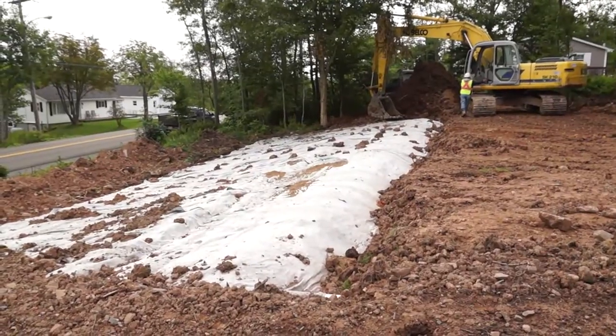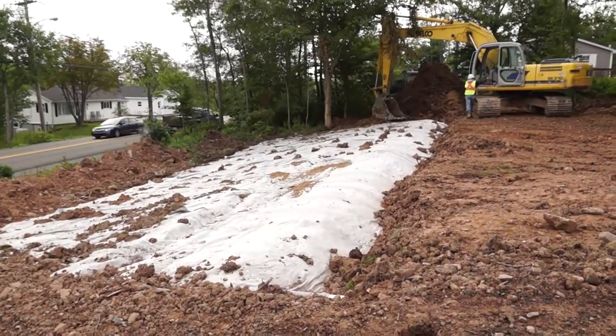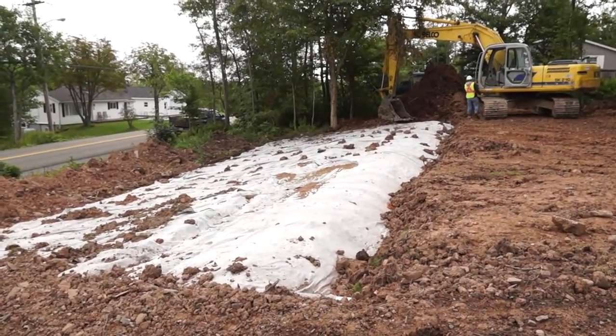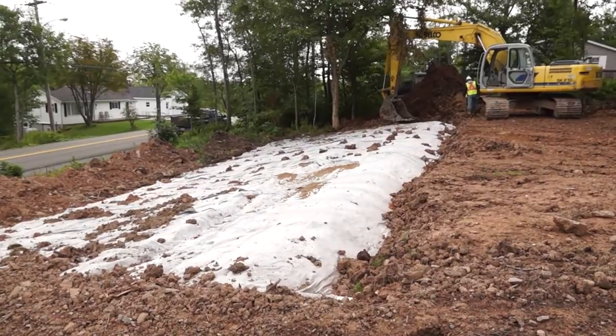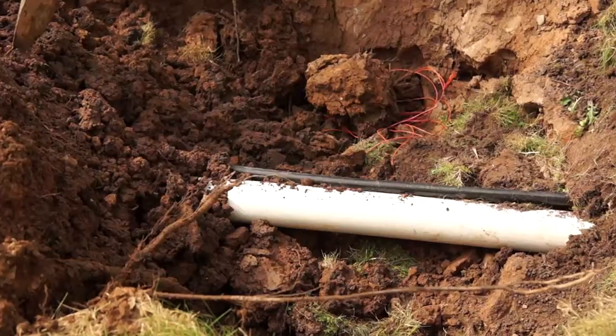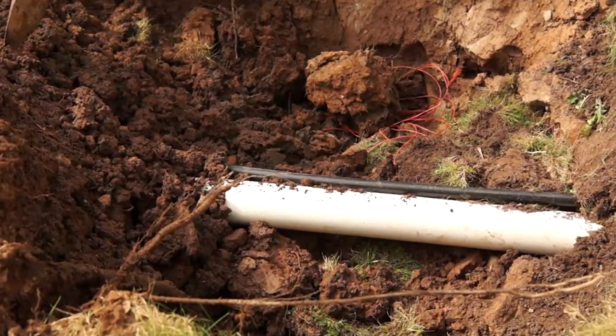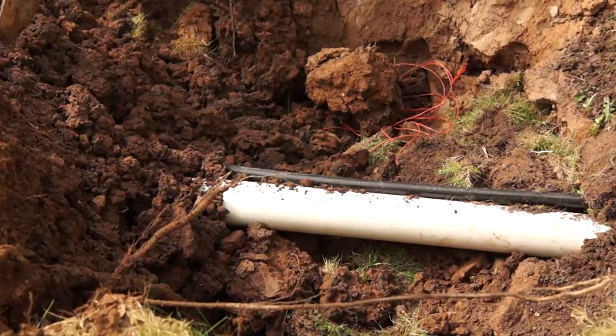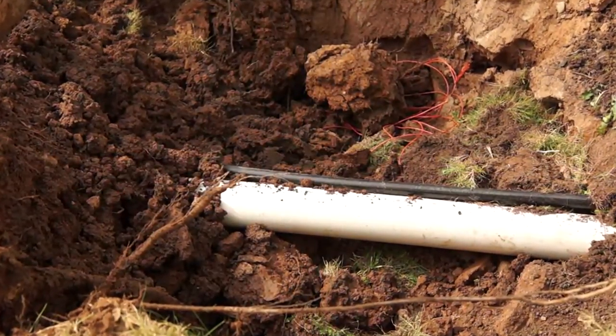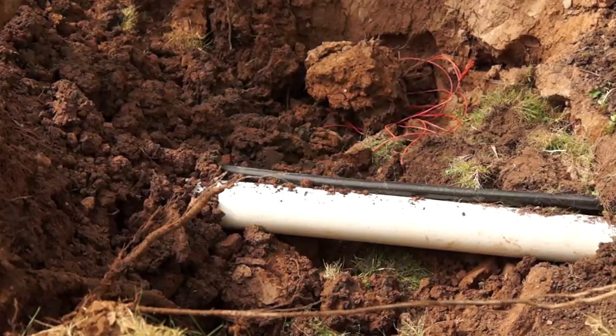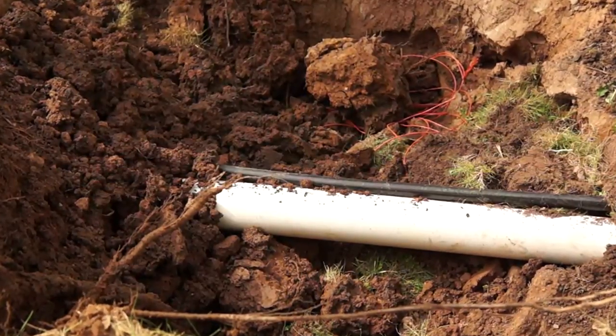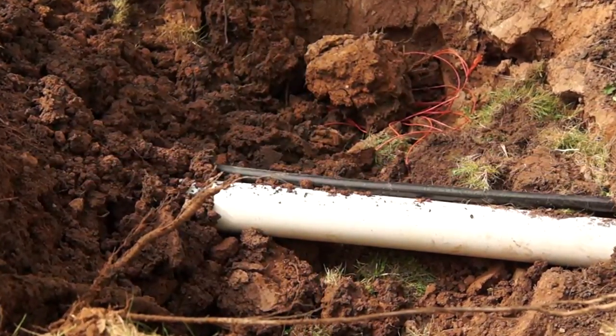The distribution trench and filter bed are covered with a geotextile material and left open. Water softener discharge may cause problems with the septic system. The water softener discharge has been removed from this system, and a second line has been installed to take the discharge away from the septic system to another area of the property for disposal.